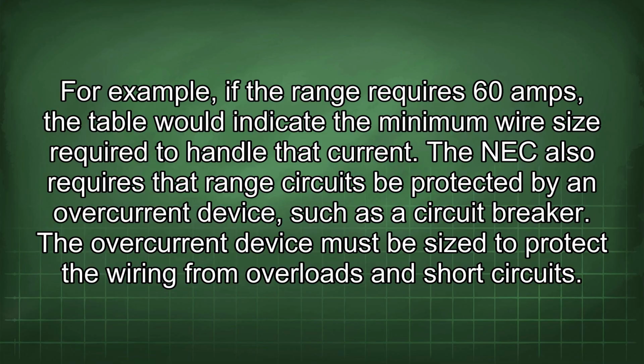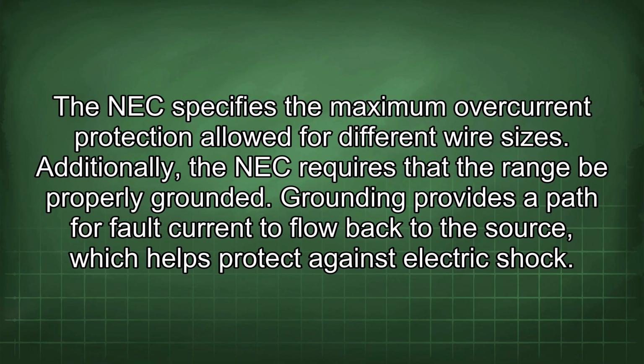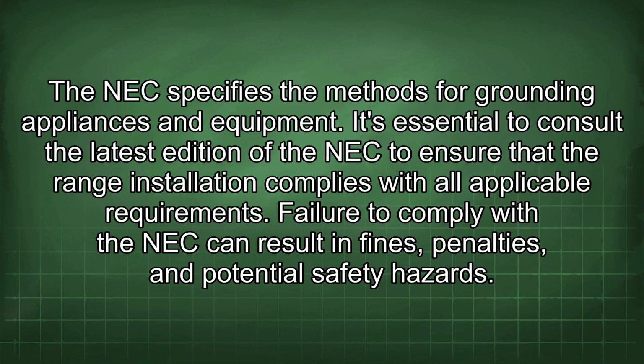The NEC also requires that range circuits be protected by an overcurrent device, such as a circuit breaker. The overcurrent device must be sized to protect the wiring from overloads and short circuits. The NEC specifies the maximum overcurrent protection allowed for different wire sizes. Additionally, the NEC requires that the range be properly grounded. Grounding provides a path for fault current to flow back to the source, which helps protect against electric shock. The NEC specifies the methods for grounding appliances and equipment.